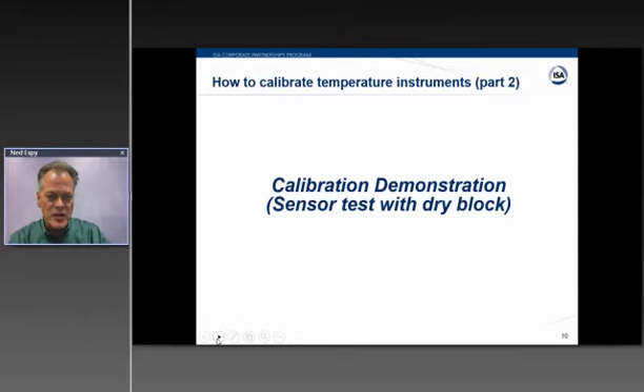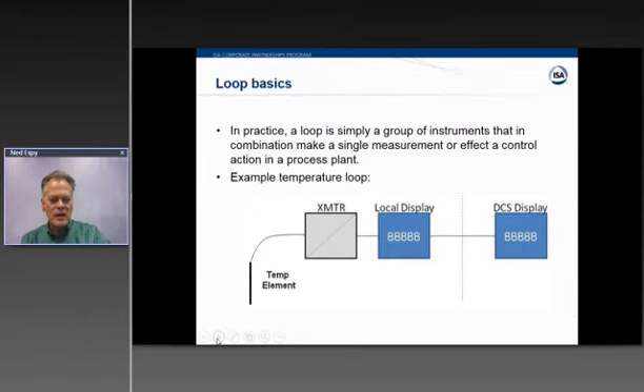So that was Roy's demonstration. We're going to change channels a little bit here. Roy kind of touched on it, but I want to talk a little bit about loop testing. This is a very common practice with temperature. It's one thing to test, as in this drawing here, the temperature element, or disconnect the element and check the transmitter. You might disconnect the local display and shoot a signal into the DCS and so on. But when you look at a loop, which is a group of instruments that are making a single measurement within your process and that affects some type of control action, really what matters in your process control is what the DCS display is, and is it displaying true temperature as measured by the temperature element at the other end of the loop.